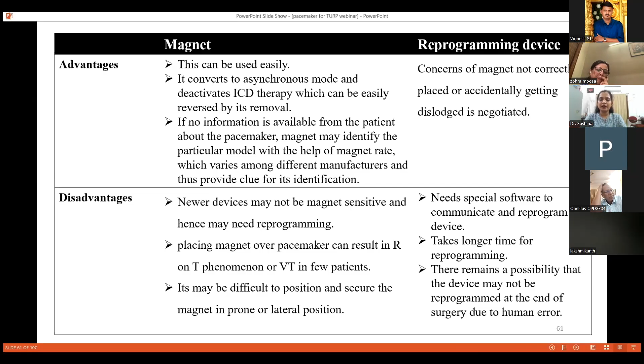Coming to reprogramming software, the advantage is that the concerns of the magnet, like not being correctly placed or accidentally getting dislodged, are negated here. The disadvantages are that it needs special software to communicate with and reprogram the device. It takes longer time for reprogramming, and there remains a possibility that the device may not be reprogrammed at the end of the surgery due to human error.